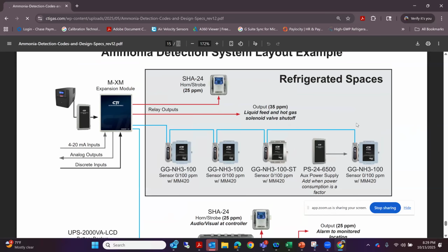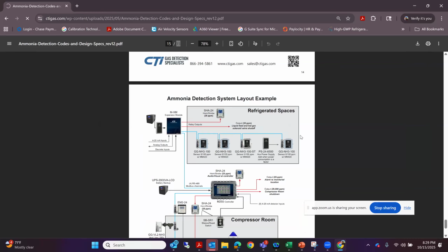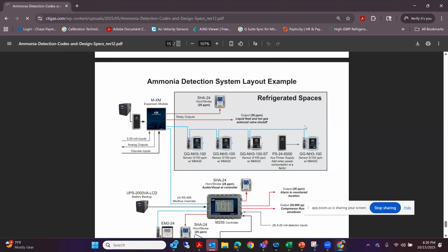Well, what is nice about Modbus is that you can come right out of here and go back out, and you can add more sensors to that chain. You don't have to come back to where this controller is located. This controller might be over in the MCC area or in the refrigeration office area, clear over here, another 400 foot on the other side of the building. While you're trying to pick up sensors another 700 or 800 or 900 foot on this side of the building, it makes a lot more sense to just pull wire from your last cooler to your next cooler to your next cooler and add those sensors in that way.